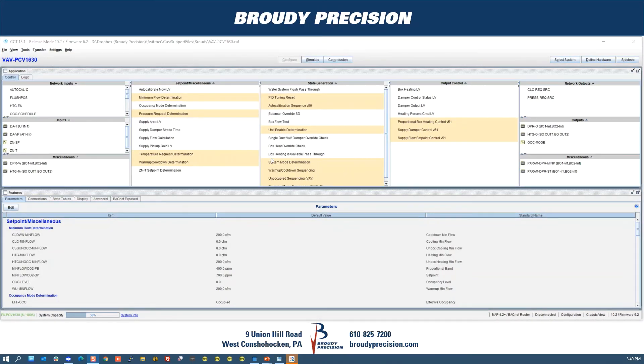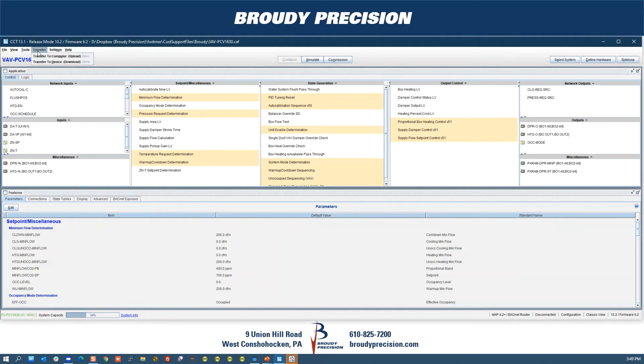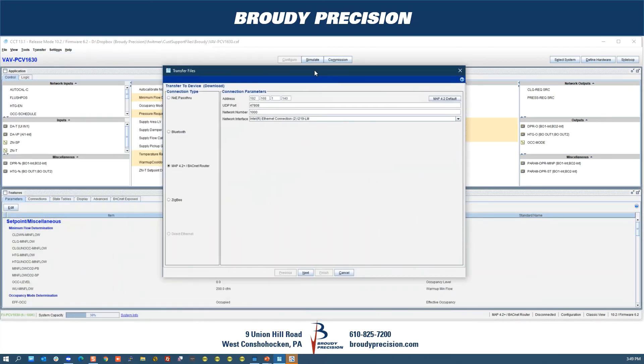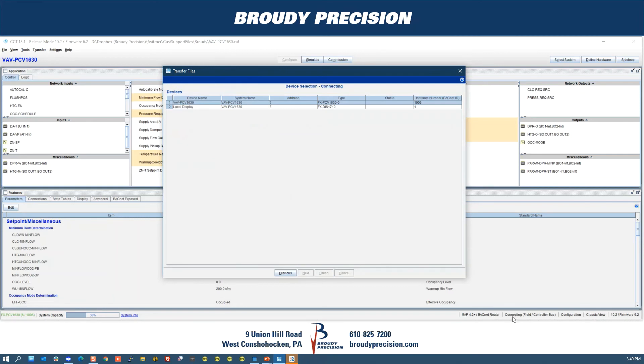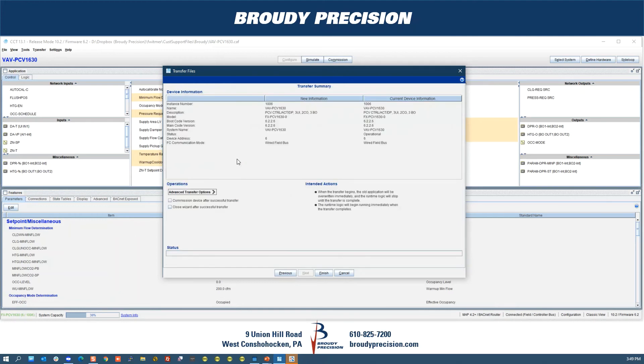In CCT, we have our application — a PCV 1630 in this case. We go up to Transfer, then Transfer to Device. We verify our settings: our IP address is correct, we're using the standard UDP port, the network number for the MSTP port of the JACE is 1000, and we're using our Ethernet connection. We hit Next, and as we wait for it to connect to the JACE — acting as the router — it should come up and allow us to do a download.